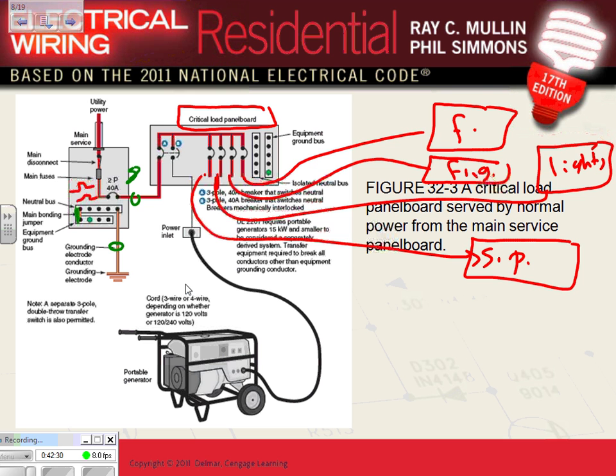Long story short, if you tie to the grid without being in sync, it will burn your equipment. Period. Okay, so that's number 1. Number 2, the other reason, guys, so you're guaranteed you're not tying with the grid when it's running, number 1. Number 2, if the grid is off, you also don't want to feed power back into the grid and kill the lineman who's working right up on the transmission line, right up somewhere in here. Right? Because you can feed back into the system. So that's why we have these very important two circuit breakers, two pole each, mechanically interlock.